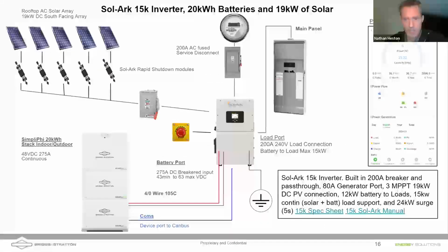For a Sol-Ark 15k, here's a nice simple example of an easy install. I'm showing it with a new stack of 6.6s there on the left, where you have 20 kilowatt hours of storage. Looking at how we're wiring this, though, we're coming in from the main meter. We're going through a service disconnect. And this should be fused or breakered with an appropriate disconnect at 200 amps. And so we can pass that 200 amps through the utility port of the inverter and then out to the loads. And then the inverter itself will supplement the power of the loads with utility power if it's needed, if the battery is low or if there's not enough solar coming in.